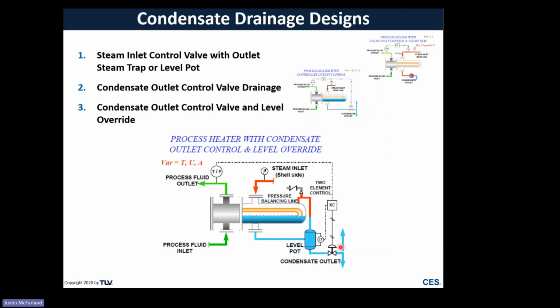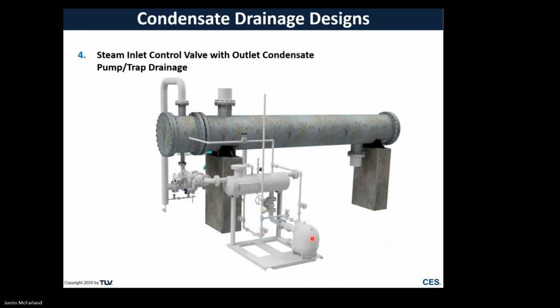I have a hybrid between that and one of the previous systems, acknowledging the risk of that blow through scenario, which is having a level override. The whole objective here is to have a kind of fail safe to monitor the liquid level downstream of the process heater, just to make sure that there's some sort of minimum set point. And the very last one, and then the main topic of conversation today, is steam inlet control valve with an outlet condensate pump trap drainage or power trap system.